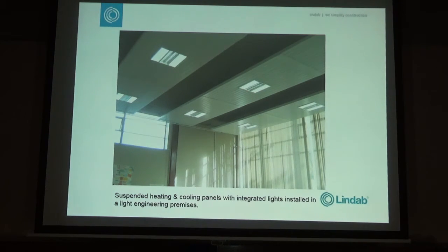Did you say a free-hanging panel is more efficient than one which is recessed in the ceiling? Free-hanging, yeah. Because you get more convective air, so if you put it in the ceiling, you restrict the convection on it. So when you remove the ceiling, it allows the hot air to rise up around the edges.